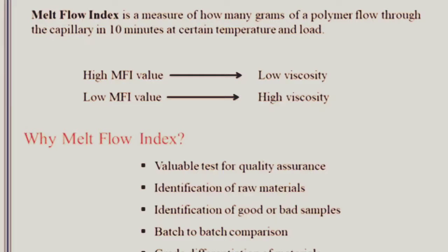A higher melt flow index indicates a lower material viscosity. This means that a material with a melt flow index of 20 flows easier than a material with a melt flow index of 5. Because if the viscosity of a material is low, the amount of material coming out through the capillary would be more, and therefore the MFI value would be higher. Similarly, if the viscosity of a material is high, less material will come through the capillary, and the MFI value for that high viscosity material would be low.